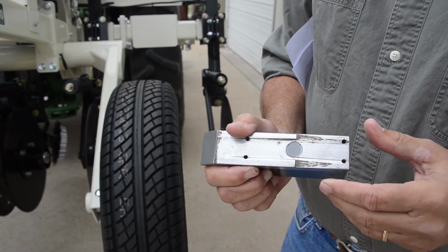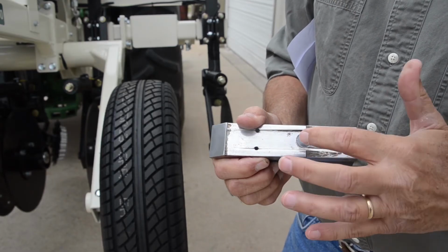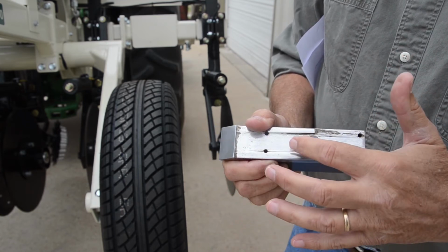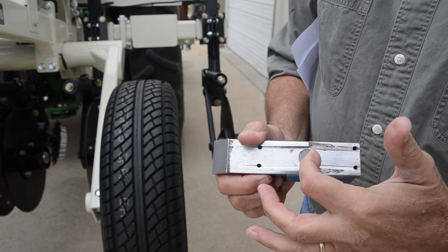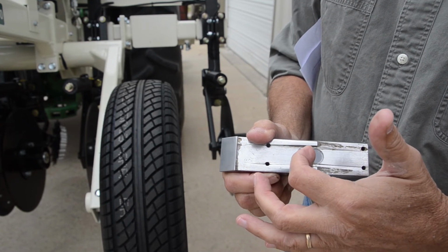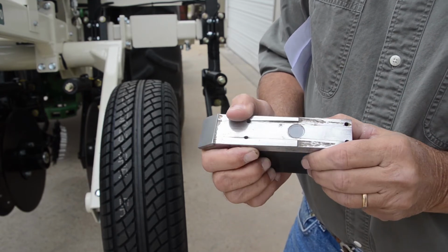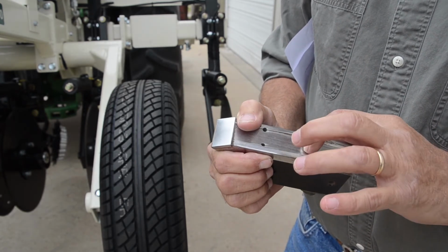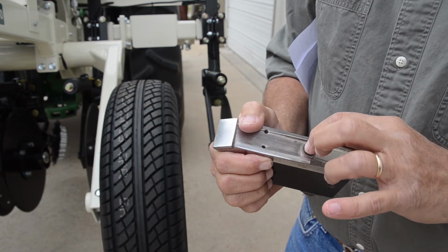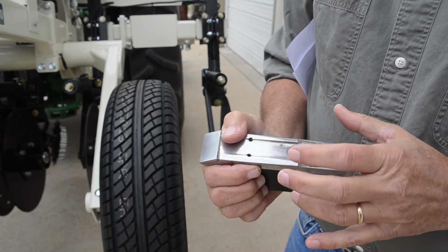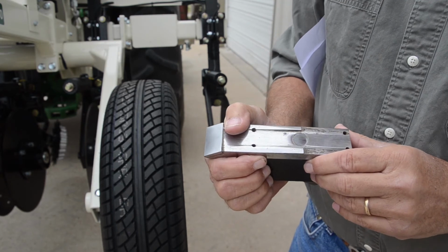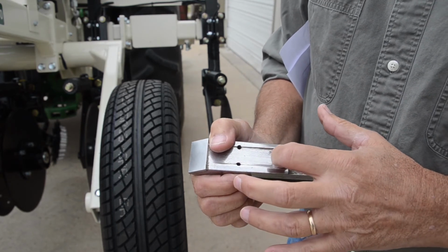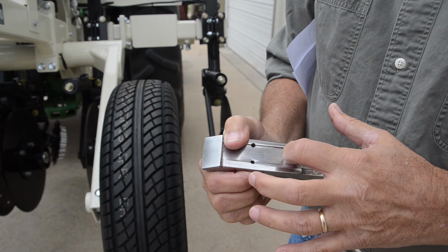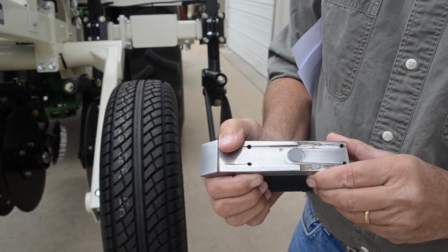So here is a well-worn wear plate. You can tell the edges are worn down, and if you run your finger across here, you can definitely feel that window now protruding. You can run it a little longer than this. You can probably run it until it actually starts frosting a little bit at the front edge there, but you're on borrowed time when you get to that point. So it's best to replace this when you can really feel that window protruding from the wear plate.